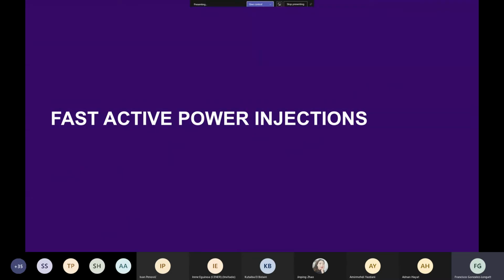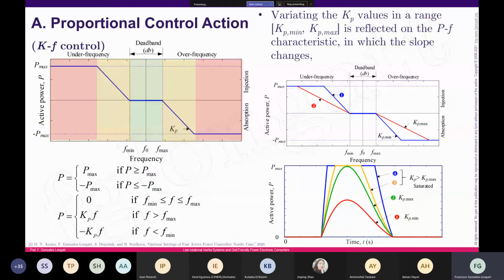Fast active power injection is a frequency controller. It's very sensitive to the frequency. We are using basically two different control actions: proportional control action and derivative control action, okay? The idea of using the proportional control action is solving the problem of the activation. When we have a proportional control action, we can include a dead band. And if we are inside the dead band, okay, the contribution is 0. But if we have an under-frequency or over-frequency event, we can use this proportionality to produce electrical power and try to compensate the power imbalance. And when we reach a maximum, we stop, okay? We keep delivering the maximum power.